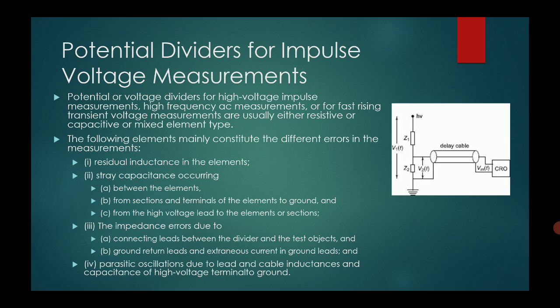Next we'll talk about potential dividers for impulse voltage measurement. Previously we have seen potential dividers for AC and DC. Now we are using potential dividers for impulse voltage. The schematic diagram is shown on the right. The potential or voltage divider for high voltage impulse measurement, that is high frequency AC measurement or fast rising transient voltage measurement, is usually either resistive, capacitive or mixed.